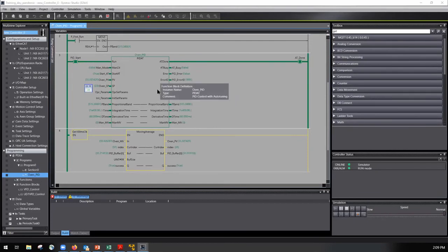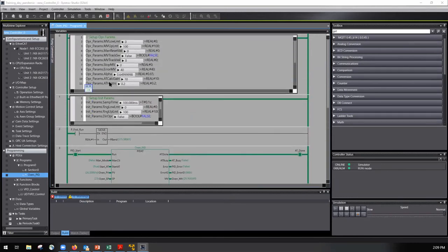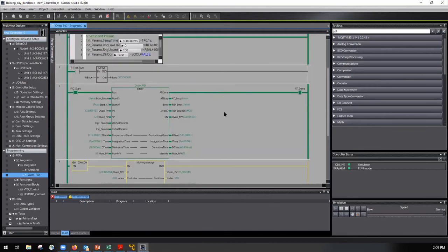But if this were, say, a pressure washer, where it's very quick to react, we would actually adjust our AT calcgain parameter here from 10 to 5, something like that. You can try different ones as you tune it. 10 is very slow, very smooth, which, as you can see, is a pretty smooth, pretty slow to respond PID block. That's something that we want for an oven.